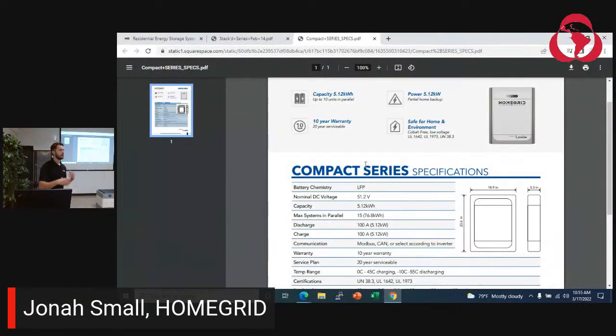We see a lot of these used in smaller homes or apartment complexes and multifamily buildings where they want to put a small battery in each unit. We've also had people building out RVs and things like that use them. Each of these is 5.12 kilowatt hours - so 5 kilowatt hours, and this is an old spec sheet, I apologize. We can actually do up to 15 of these in parallel, so we could do 15 of them on a wall. However, I tell people that unless you need it on the wall, once you use more than 2, you should use the stack series because it's much easier to upgrade. So if you're doing 1 or 2 of these, it makes sense.